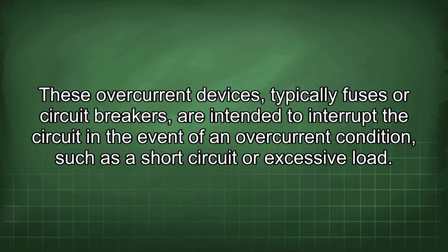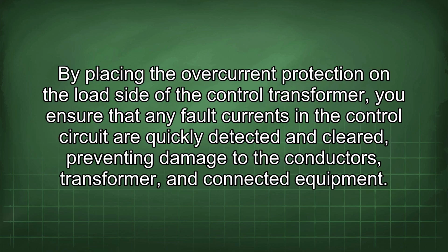These overcurrent devices, typically fuses or circuit breakers, are intended to interrupt the circuit in the event of an overcurrent condition, such as a short circuit or excessive load. By placing the overcurrent protection on the load side of the control transformer, you ensure that any fault currents in the control circuit are quickly detected and cleared, preventing damage to the conductors, transformer, and connected equipment.